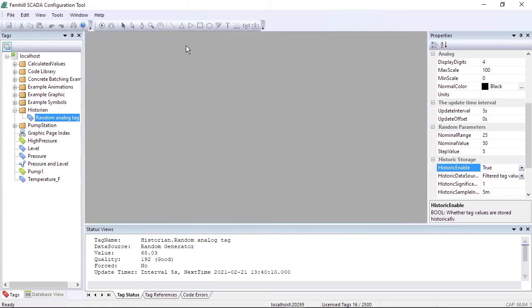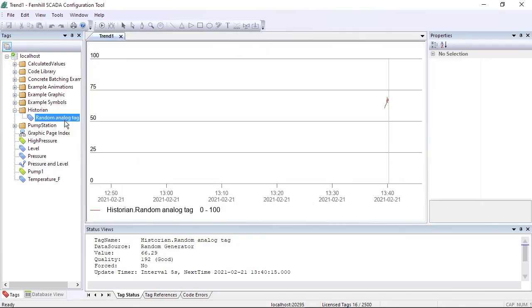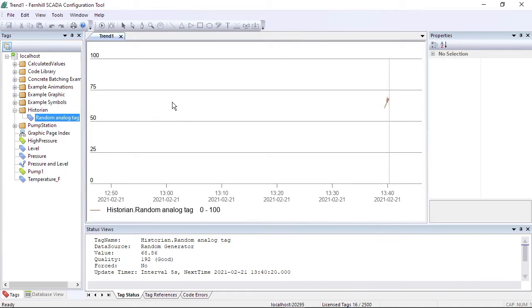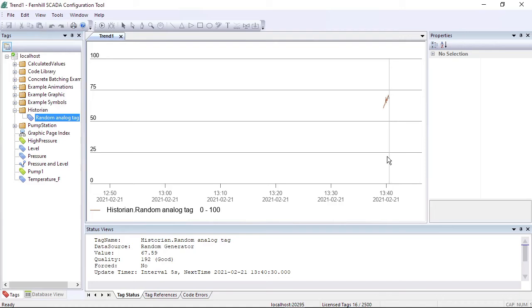Let's close the historic list and instead open a temporary trend from the data point tag. In Fernhill SCADA a trend consists of a plot area showing the data and a pen area showing details of each trace. For a temporary trend the x-axis interval is one hour and shows the most recent data, and tracking mode is on so as new data arrives the trend updates to show the new data.